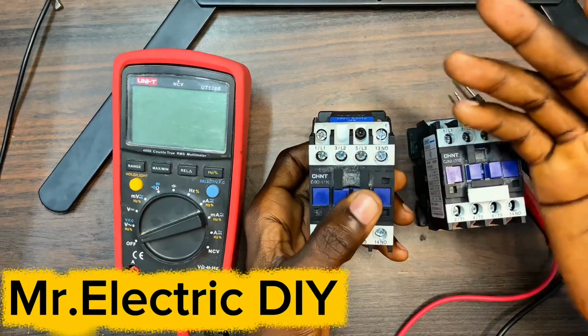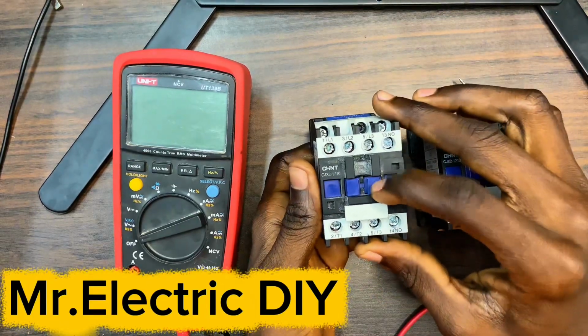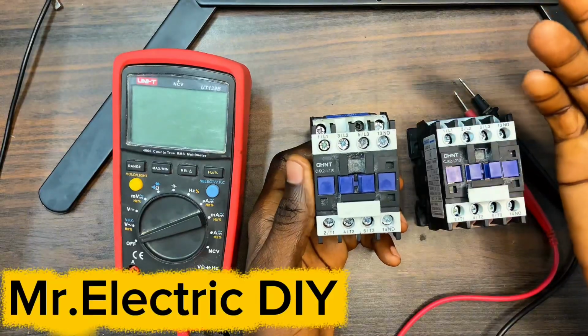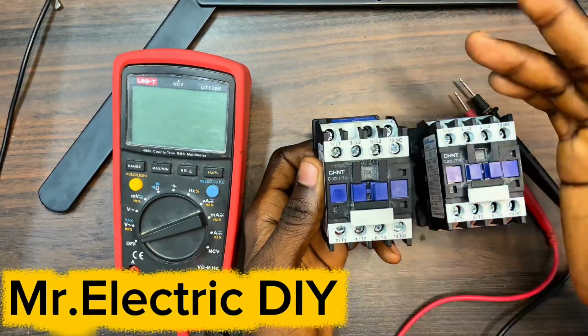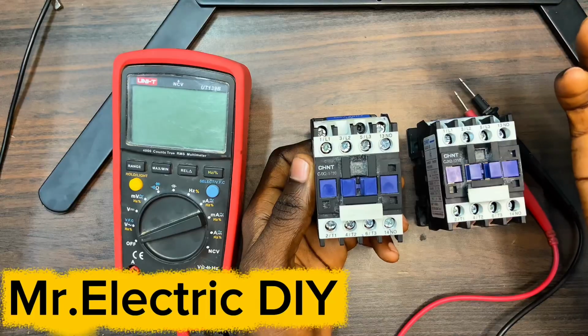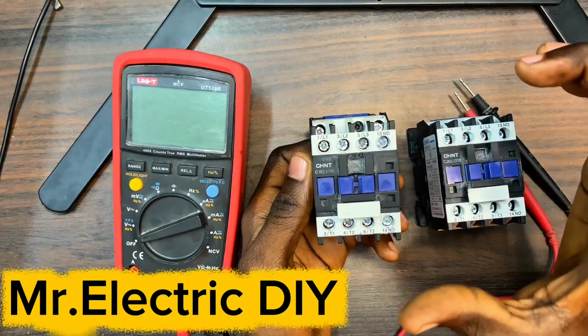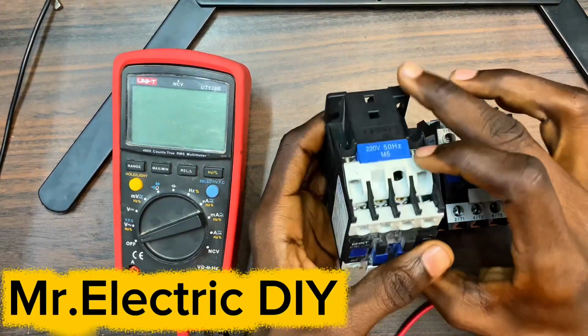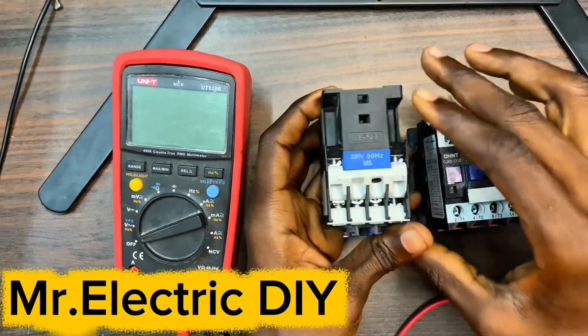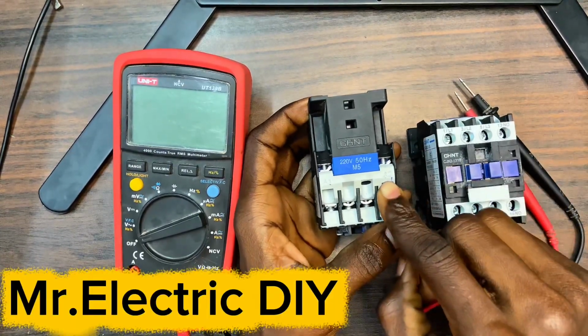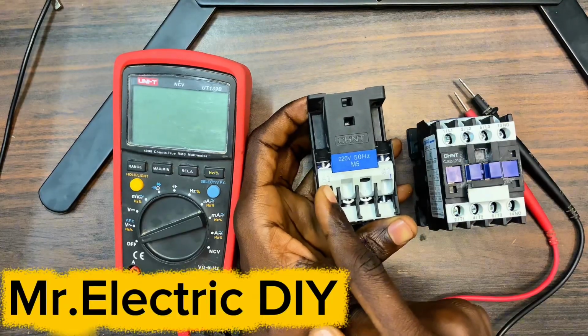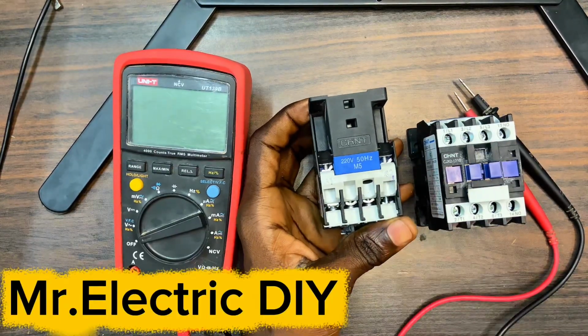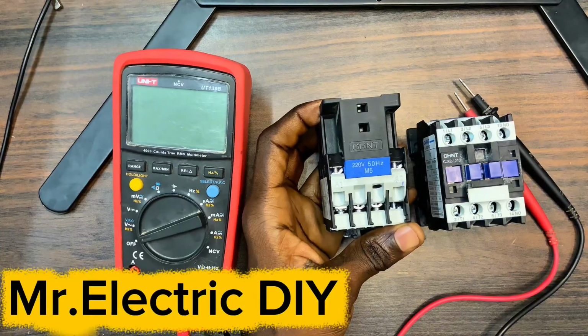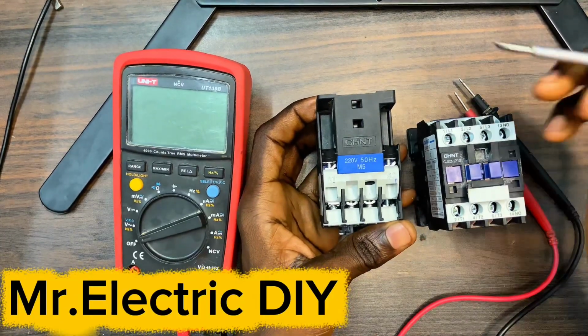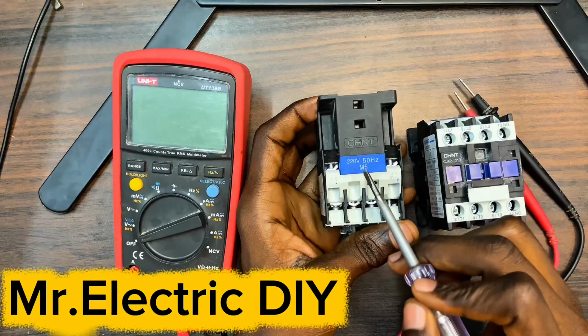Now, when you are using a push button or a selector switch to turn on this magnetic contactor and you realize that the magnetic contactor is refusing to start, it is not energizing, the only thing you have to do first is to come straight to the coil. And with the coil, we have A1 and A2. A1 is where you are supposed to connect your live wire, and A2 is where you are supposed to connect your neutral.